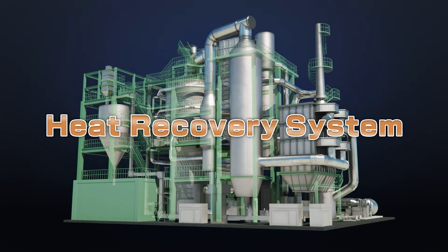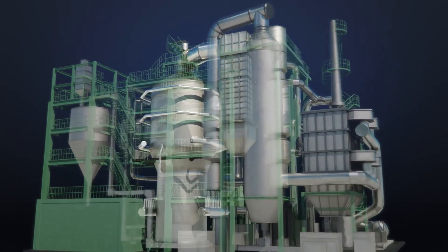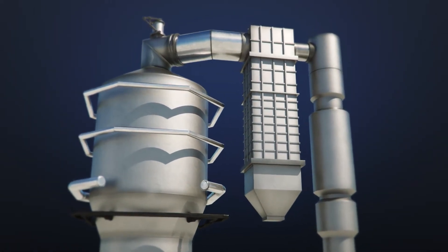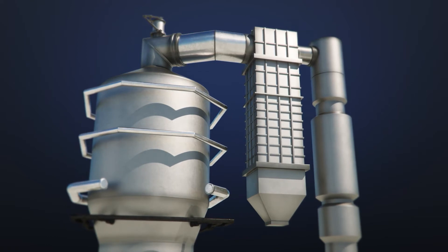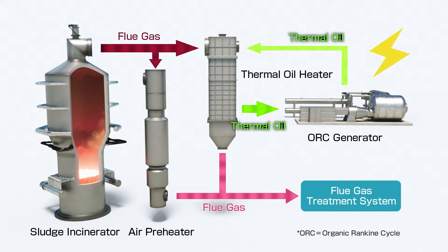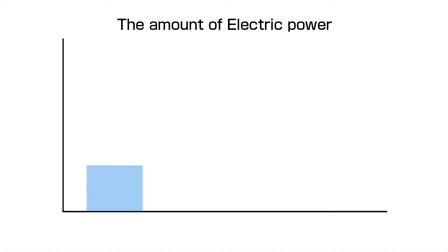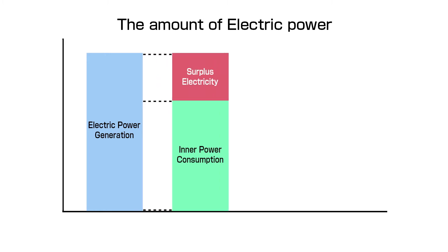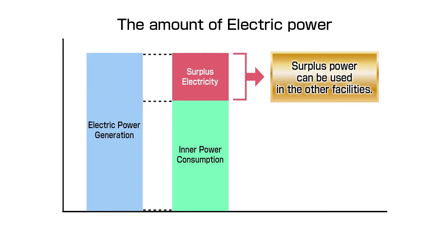The first part is a heat recovery system. This uses a thermal oil heater which enables us to minimize the size of the plant and recover heat positively. Heat recovery and the amount of power generation can be maximized by arranging the thermal oil heater and air preheater in parallel. This creates approximately 1,000 kilowatts of power generation, which exceeds the inner plant consumption, and surplus power can be used in other facilities.